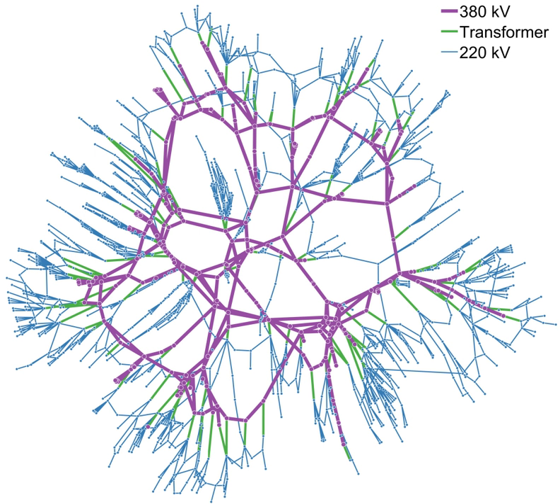The physical layout is often forced by what land is available and its geology. Distribution networks are divided into two types: radial or network. The simplest topology for a distribution or transmission grid is a radial structure — a tree shape where power from a large supply radiates out into progressively lower voltage lines until the destination homes and businesses are reached. However, single failures can take out entire branches of the tree.